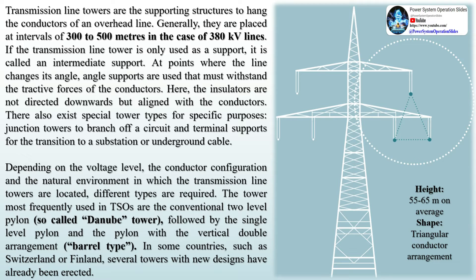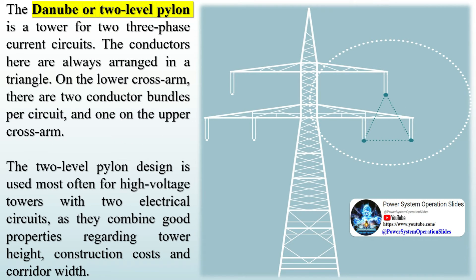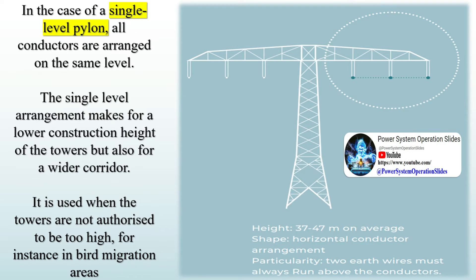Transmission line towers are the supporting structures used to hang the conductors of an overhead line. Generally, they are placed at intervals of 300 to 500 meters in the case of 380 kV lines. If the transmission line tower is only used as a support, it is called an intermediate support. At points where the line changes its angle, angle supports are used that must withstand the tractive forces of the conductors. There also exist special tower types for specific purposes: junction towers to branch off a circuit and terminal supports for the transition to a substation or underground cable. Depending on the voltage level, conductor configuration, and the natural environment, different types are required. The tower most frequently used by TSOs is the conventional two-level pylon, the so-called Danube tower, followed by the single-level pylon and the pylon with vertical double arrangement, the barrel type.